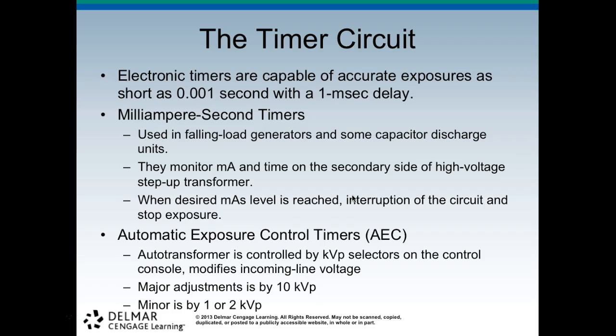They monitor mA and time on the secondary side of the high voltage step-up transformer. When the desired mAs level is reached, the circuit is interrupted and the exposure is stopped. So the automatic exposure control timers, the AECs, that's what you use all the time.